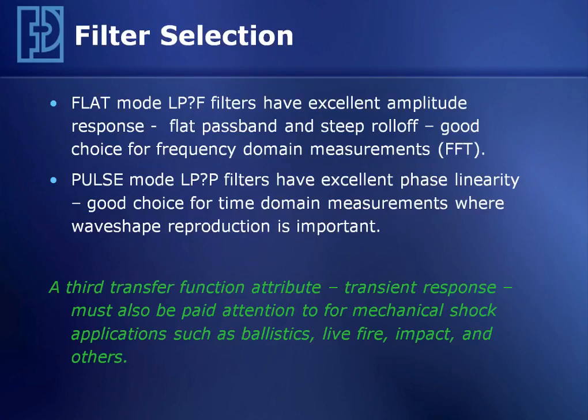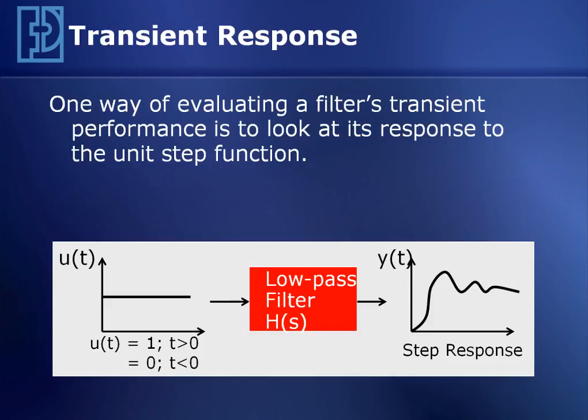I want to reemphasize that in the precision instruments, the choice of transfer function between flat, optimized for frequency domain, or pulse, more optimized for time domain measurements, is a programmable feature in our instruments. So a way to evaluate the transient response of a particular filter is to examine its step response. Step response is measured by applying a sudden DC input to the filter and then measuring the output response of that filter.